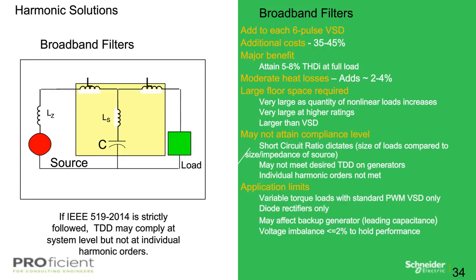So moving on to broadband filters, which offer a percent THDI reduction and can obtain levels as low as 5 to 10% THDI. These filters tend to have a very large footprint and actually exceed the physical size of the VFD on which they're applied. And their heat losses are slightly higher than the 5th harmonic tuned filter. Due to the large series impedance, these filters tend to be limited to use in pump and fan applications and to a standard 6-pulse VSD.